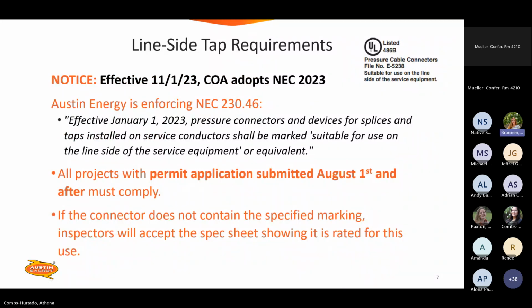Okay, I can go ahead and read through this. Line side tap requirements. I think we've gone through this a couple of times, so I'm not going to spend too much time here, but feel free to add questions to the chat if you have any. Effective as of November 1st last year, we adopted NEC 2023. We are also enforcing NEC 230.46. So effective Jan 1, 2023, pressure connectors and devices for splices and taps installed on service conductors shall be marked suitable for use on the line side of the service equipment or equivalent. So please make sure you are adding these labels as intended. All projects with permit applications submitted August 1st and after must comply.